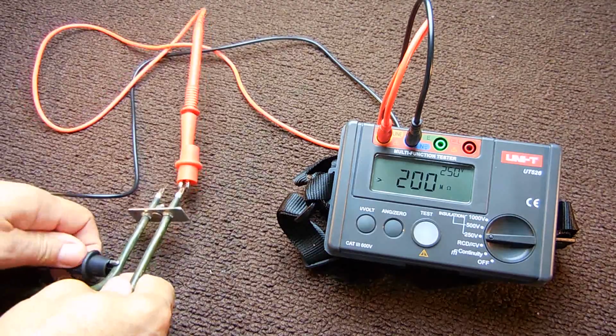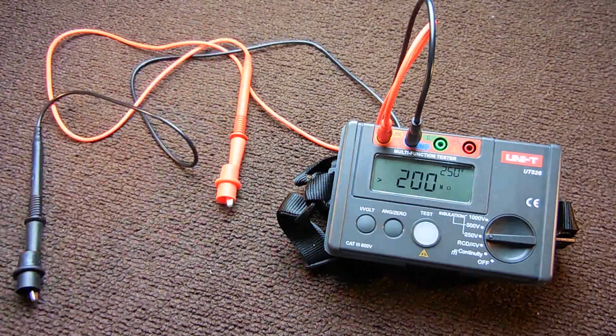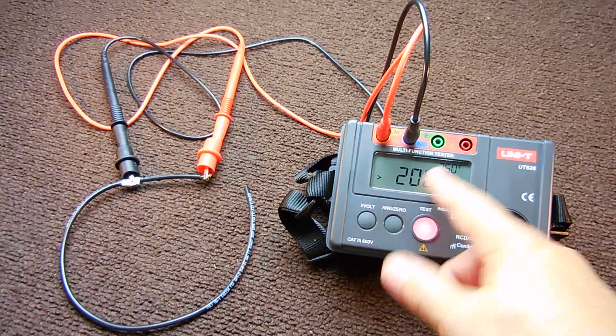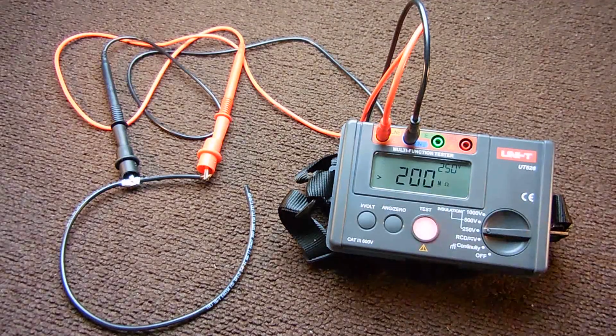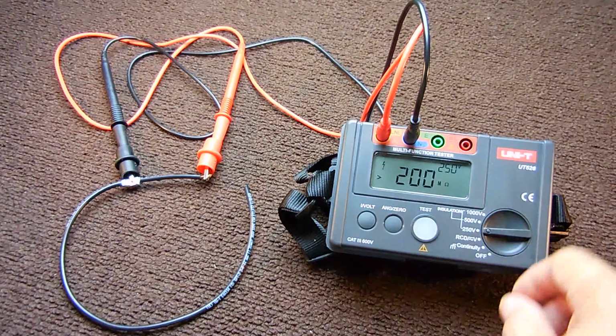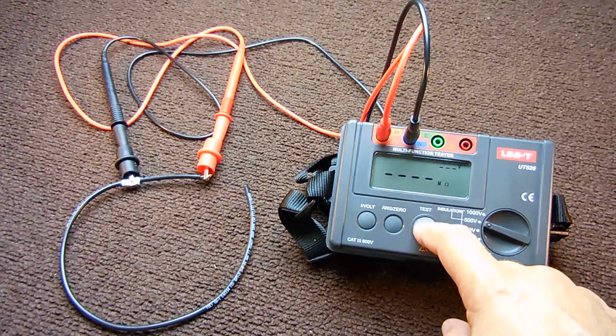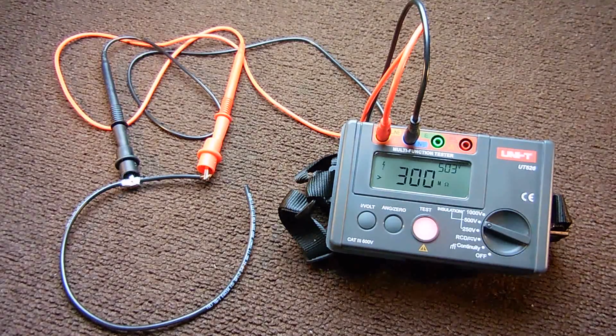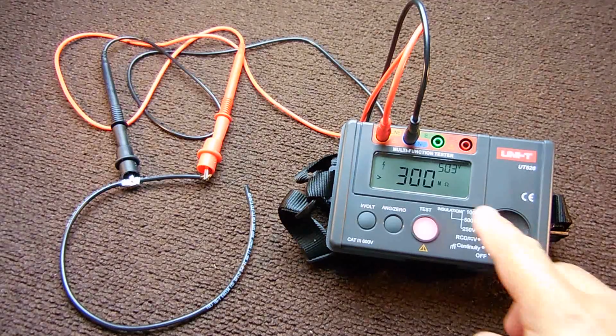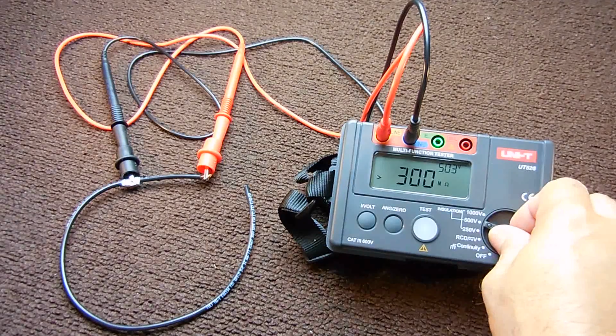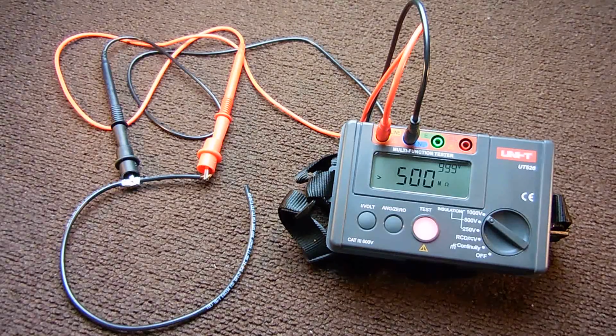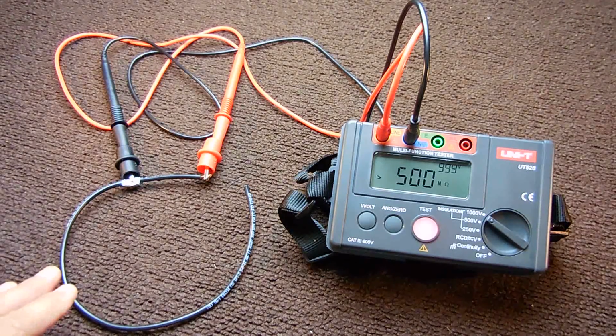Let's take a look at a wire. Here's the same test we performed earlier using the crank Megger. It showed well over 100. Let's push the test button. And this is saying it's well over 200 megohm at 250 volts. Let's switch to 500 volts just for the hell of it. Let's try it again. Here we go. And it's showing over 300 megohm at 500 volts. Let's go to 1000 on that wire. There you go. It's over 500. So the insulation on this wire is pretty good.